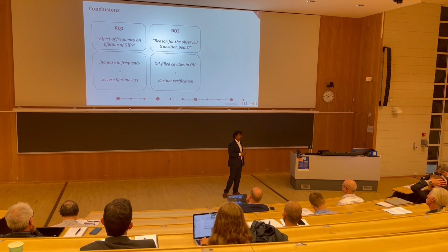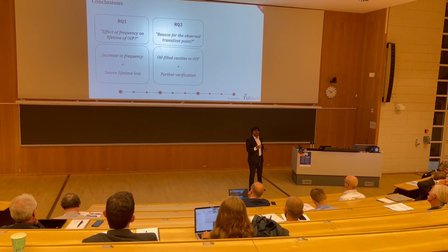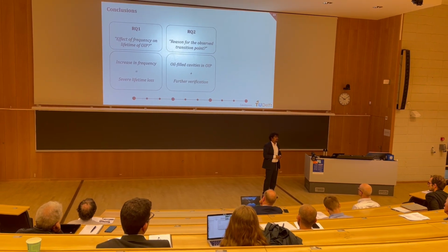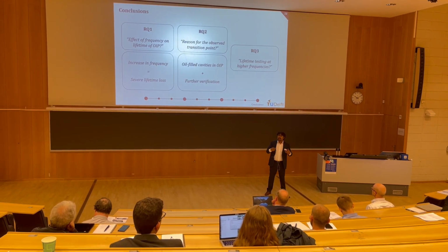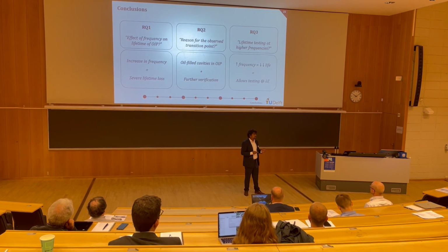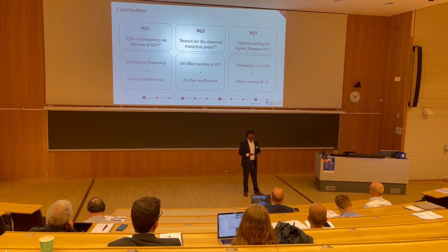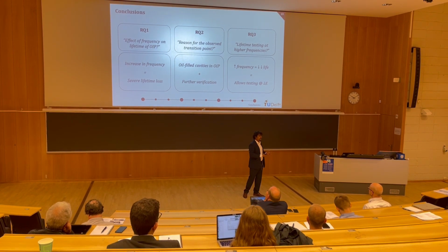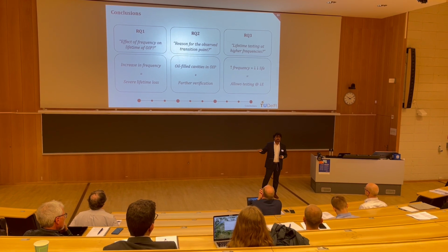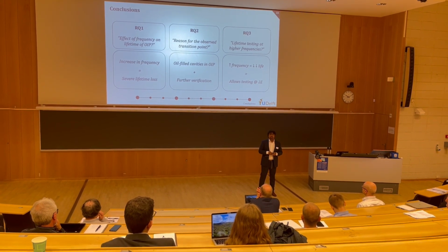One possible way of doing this is having another lifetime at 30 kilohertz and seeing if that undergoes the same transition. And finally, lifetime testing at higher frequencies taught us a very important observation that if we increase the frequency, we can allow lifetime testing at much lower values of electric field.